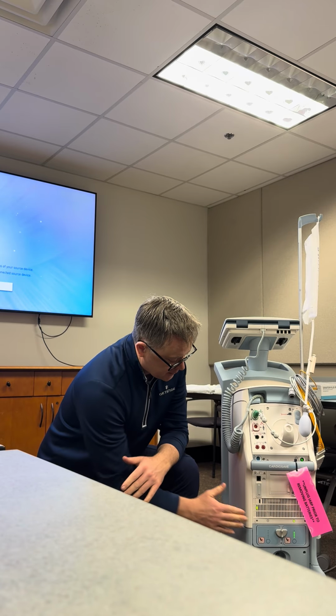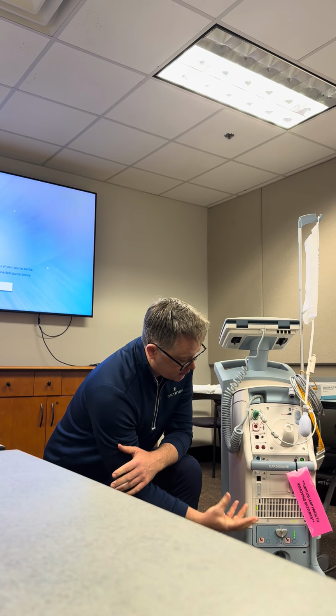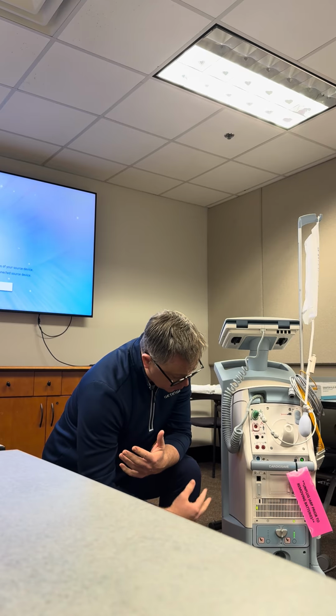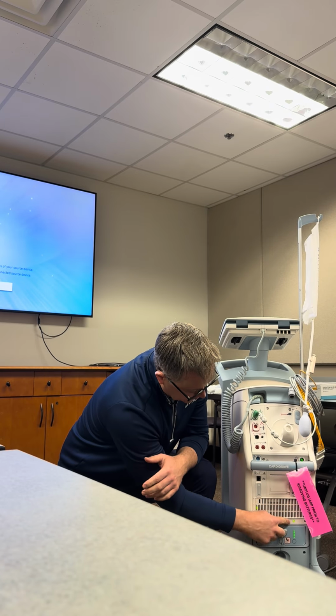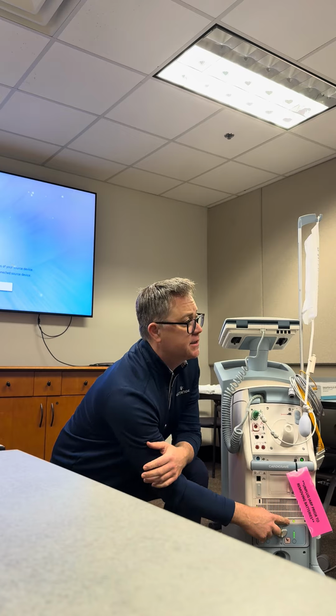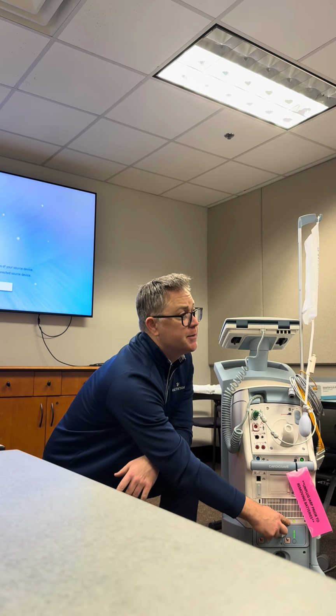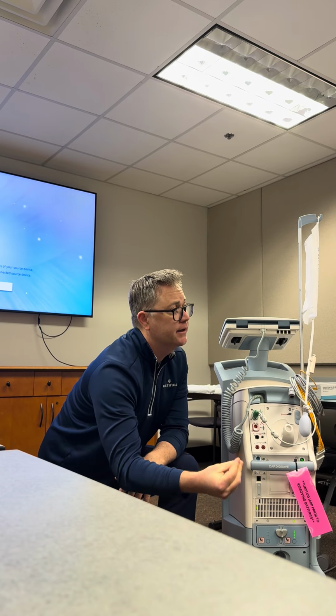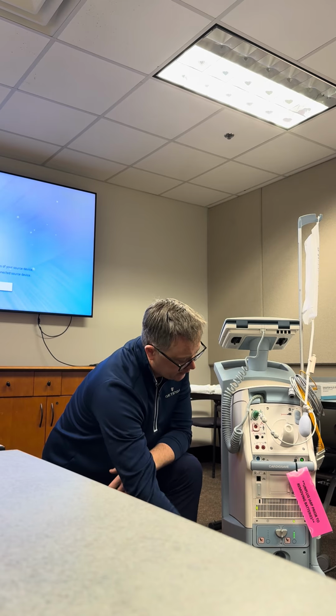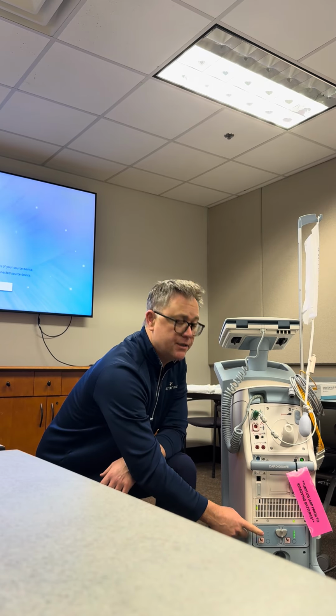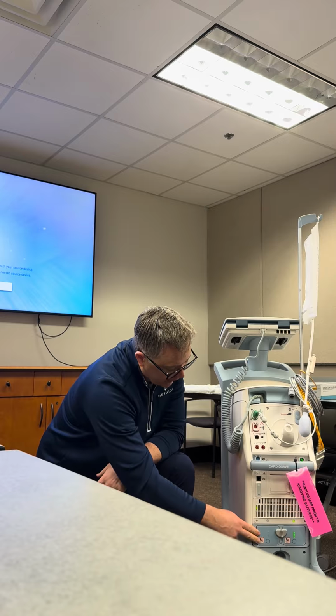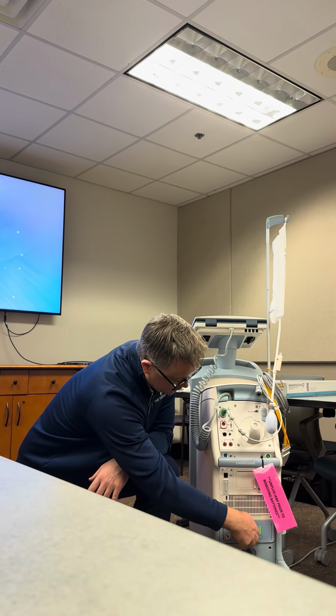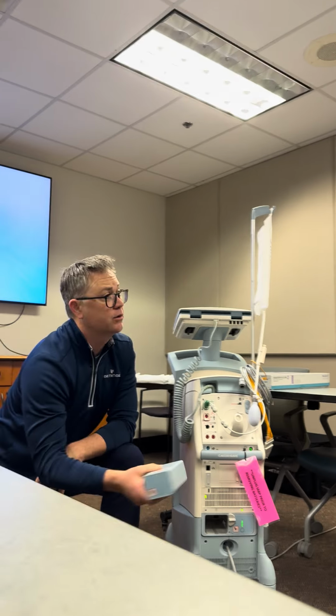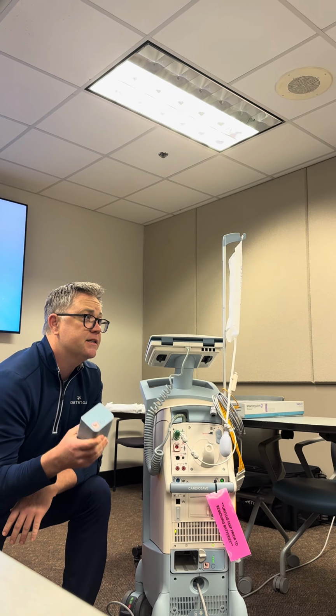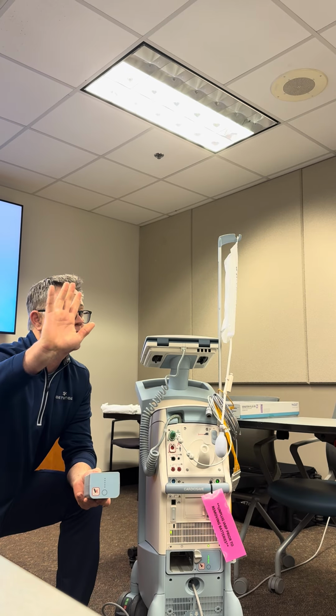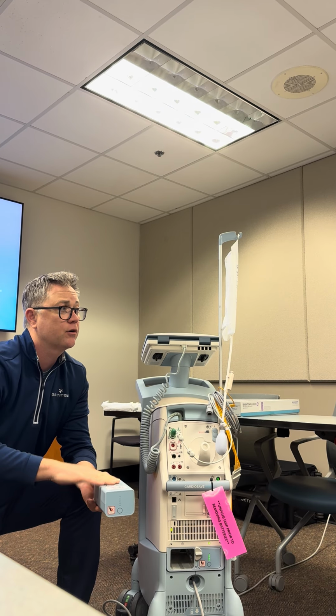So if for some reason one of these batteries doesn't get exchanged, gets old and isn't holding a charge, these do pop out. What's nice about this machine is when we're unplugged, it'll tell you which battery it's using. It'll use all of the battery capacity in one battery, and then it will switch over to the other one. So if you ever had to do a long transport, or if you had a battery that wasn't holding a charge, these are hot swappable, so you could pop one out and steal one from another unit. They're 90 minutes each, so 3 hours total to get a patient wherever you're gonna move them if you're on battery power.